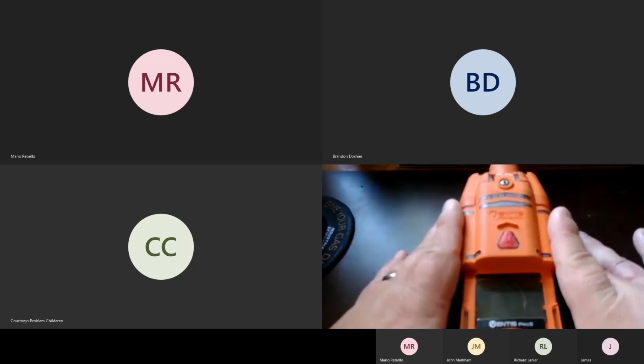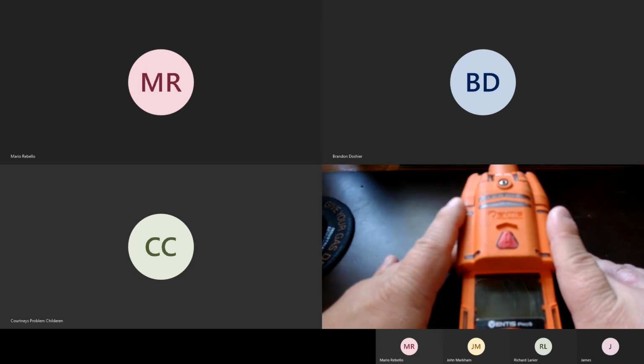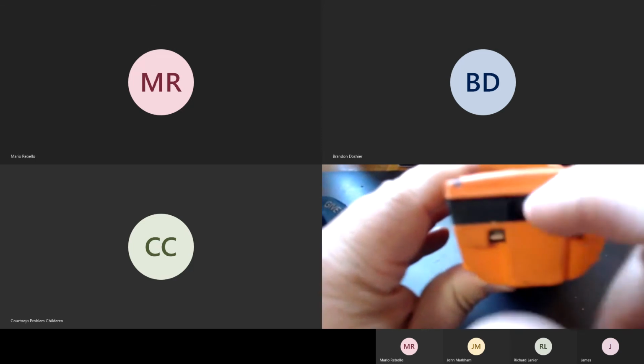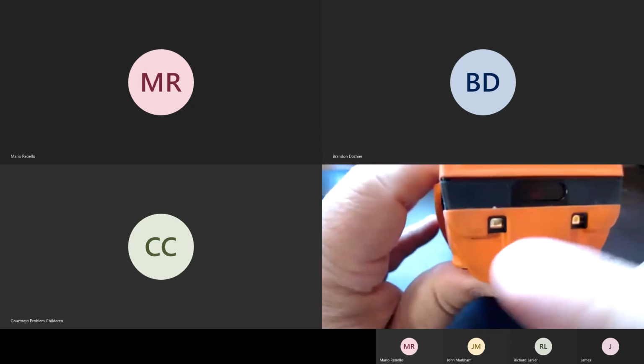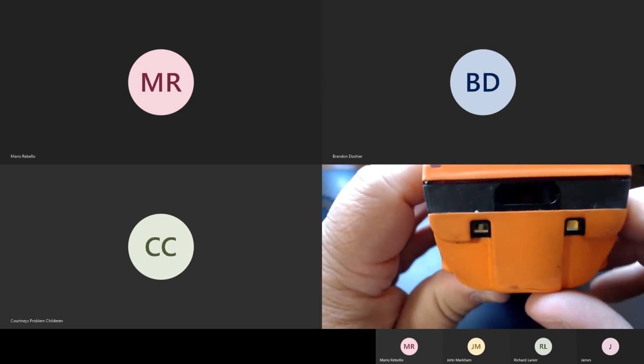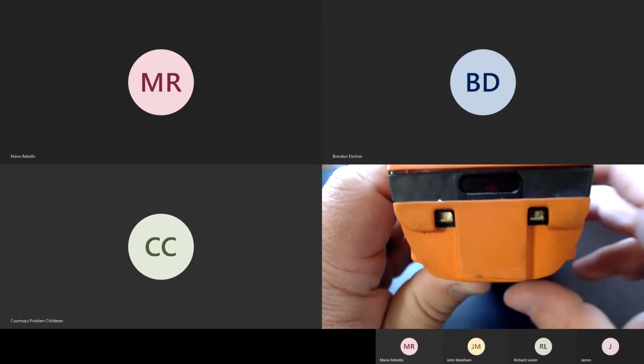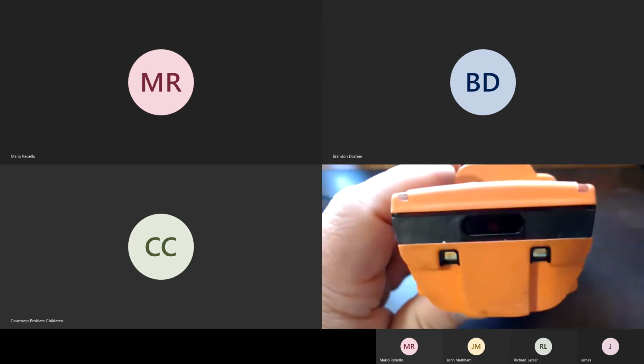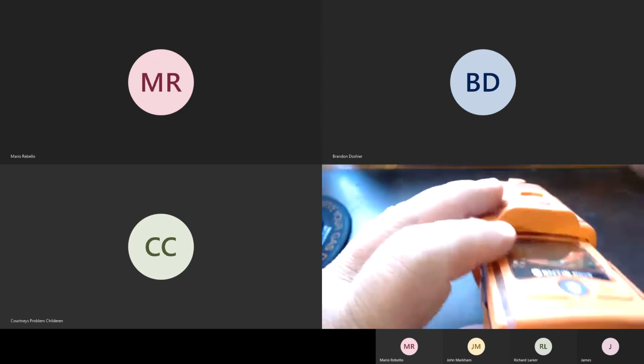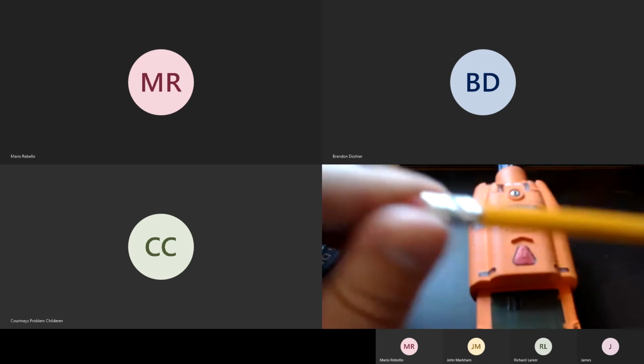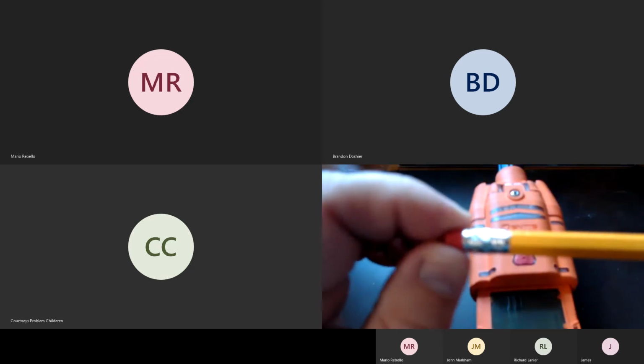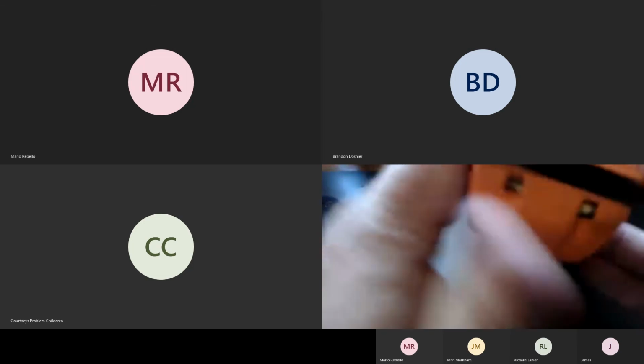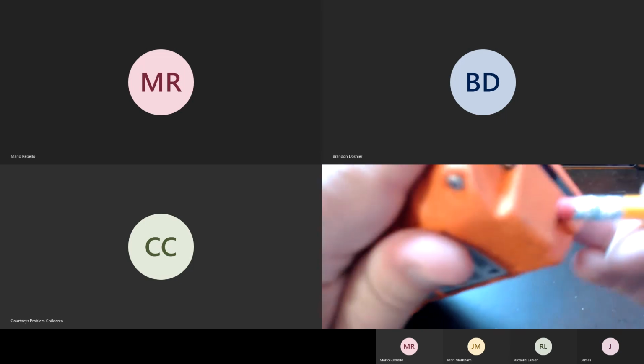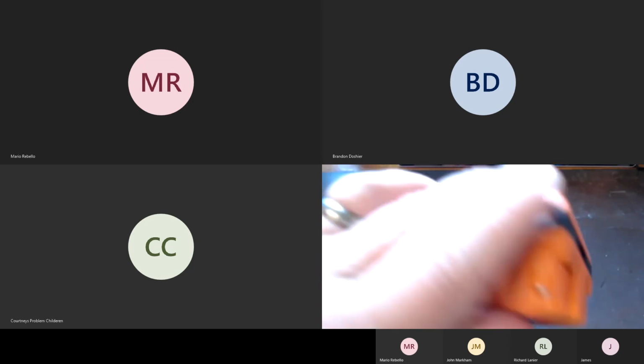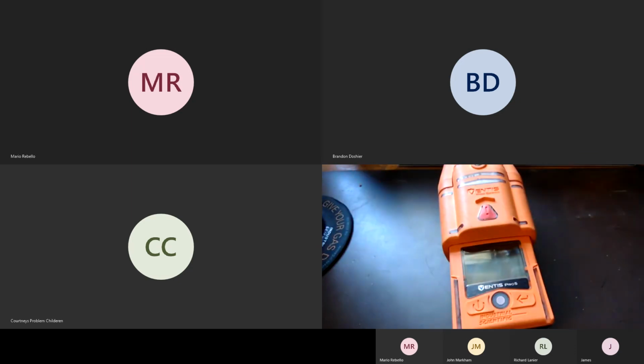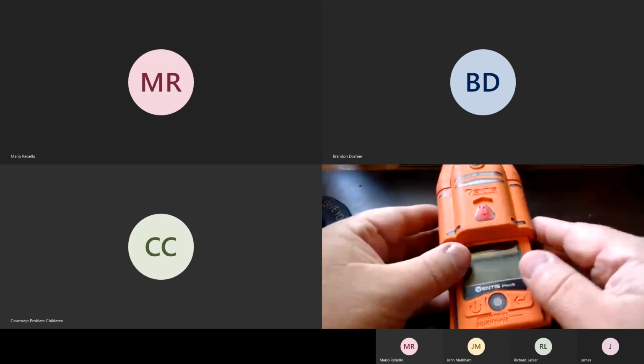So again, if the instrument gets extremely dirty, you might get a communication error on the docking station. If you do, just wipe that off right there. There you go. If you ever get any charging errors, make sure you clean off the contacts. They are gold plated, so be careful. You don't want to clean with anything too heavy or astringent. Our actual recommendation for cleaning those is a pink pencil eraser, like the ones on the end of your standard number 2 pencils, or the little wedge ones, which work best because you can get them in there. You rub that onto the gold contacts, and it cleans them very well because it has enough abrasive material to cause enough friction to clean it without damaging the gold contacts.